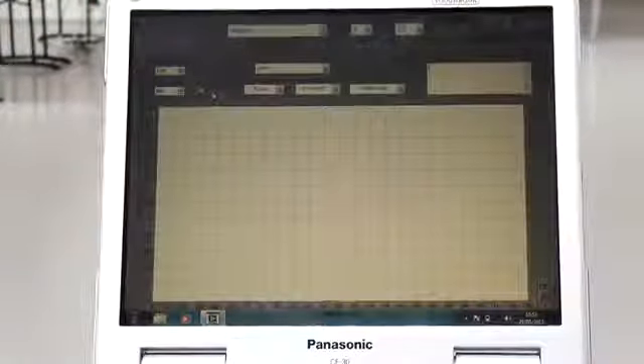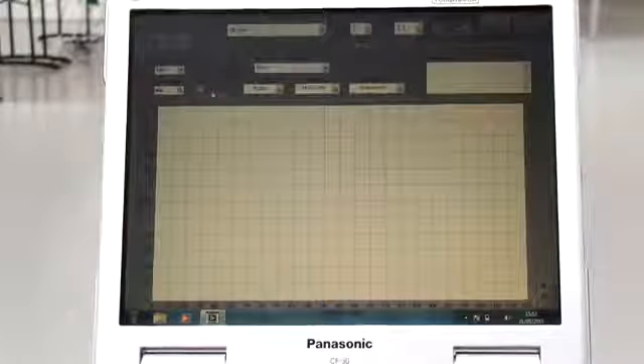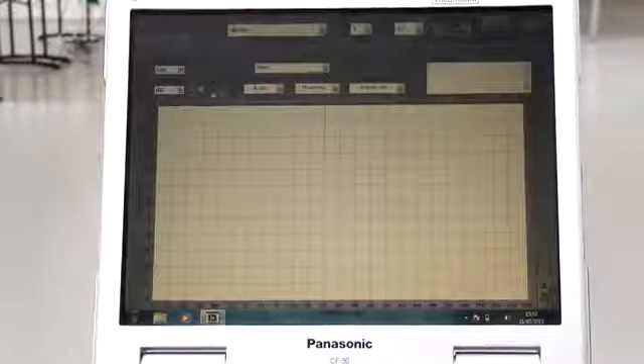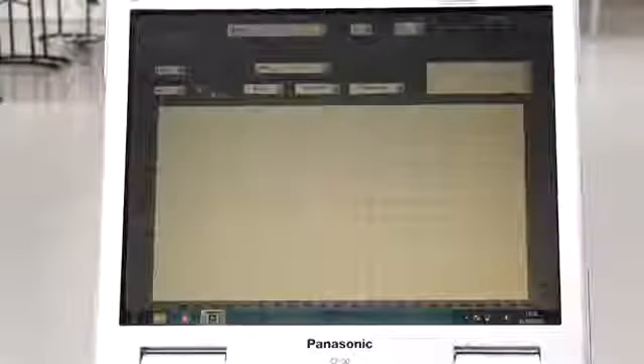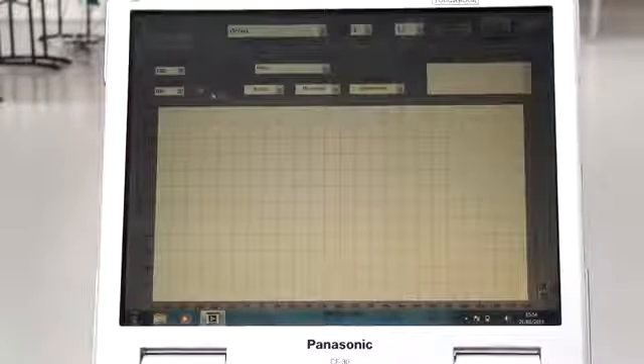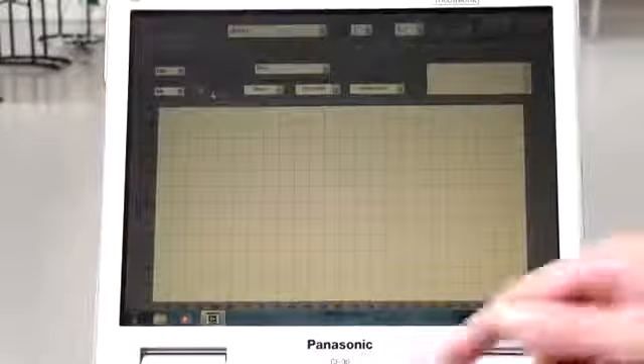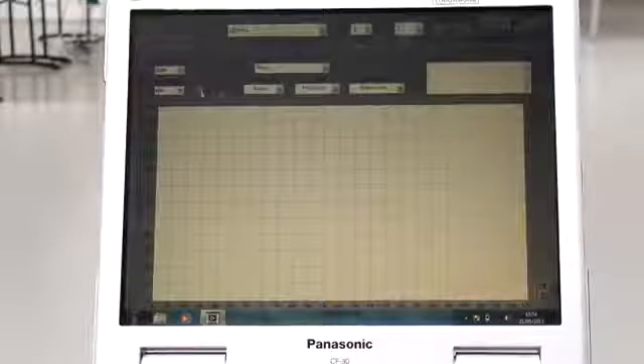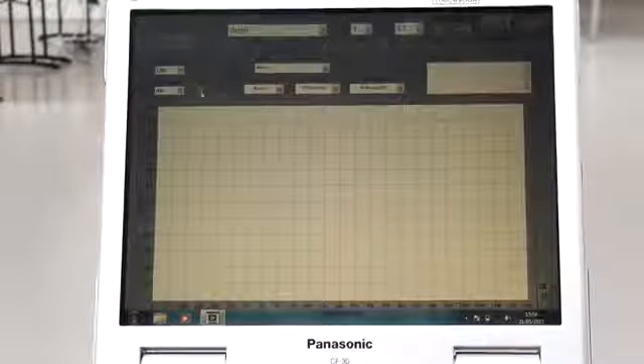End zones is a useful feature of the software. Because the scan head has an active sensor in the center of the mechanical assembly, it is not possible to get that to the edge of a scan plate. Therefore, at the edges of the plate, there is normally an unscanned area. By clicking on end zones, this allows you to scan that area to fill in 100% of the plate coverage.